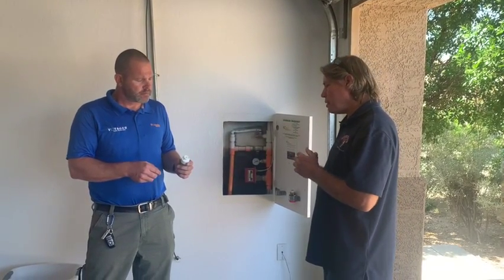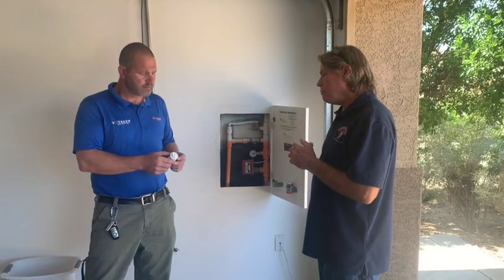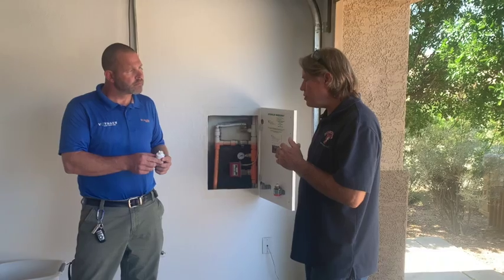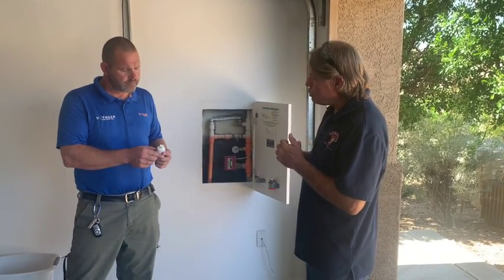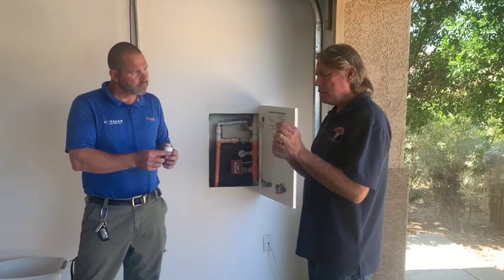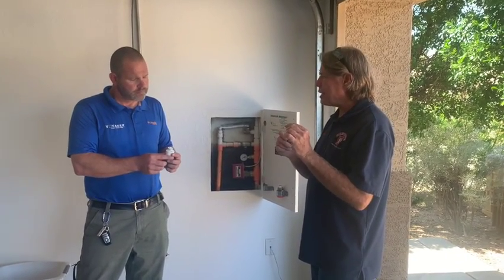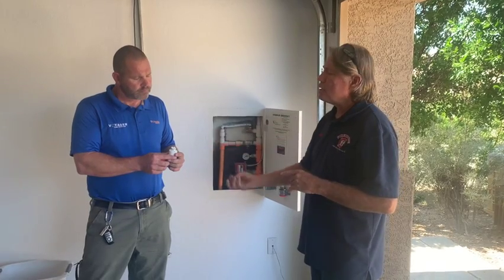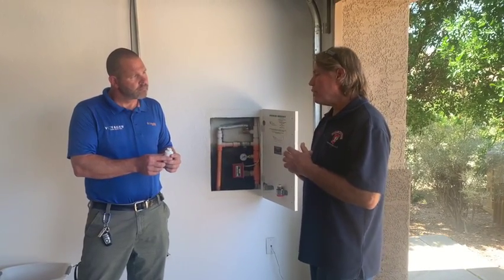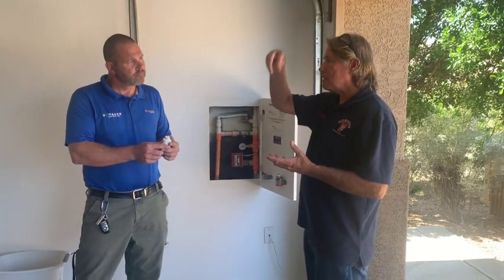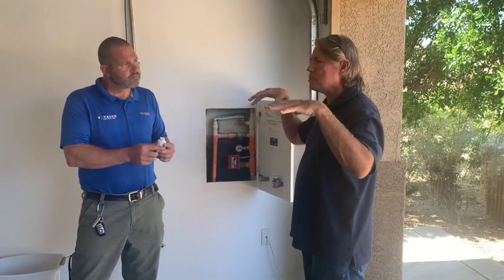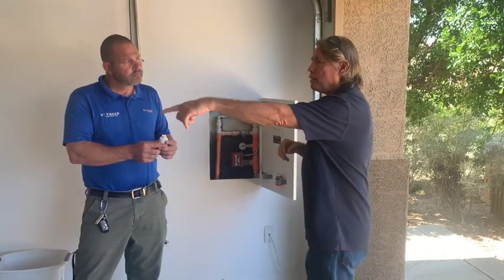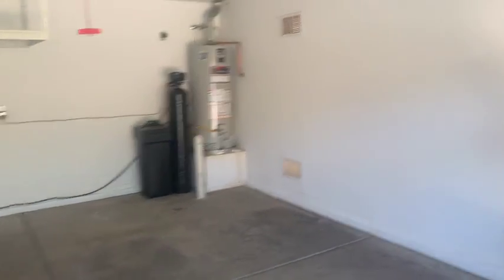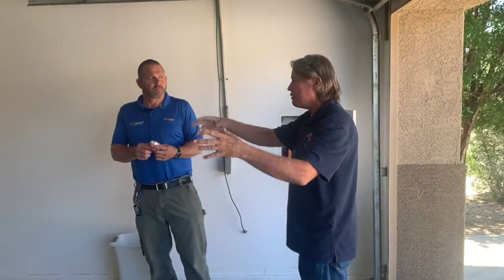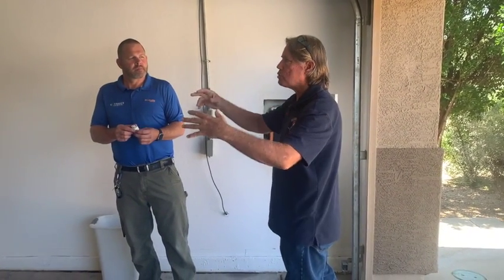Now, this particular type, the brand name is a Viking. It is a fusible link type head, so at 162 degrees, that head will deploy by virtue of solder that melts at that temperature. Then it'll release the mechanisms and allow the head to deploy. At that point, you get about 30 gallons a minute hitting a deflector that spans out in about a 10-foot radius, and it will only act individually. So if you had a fire over here in this area, for example, one head would deploy, the other head would only deploy if that head was overcome. If that sprinkler was overcome by the fire, then the second sprinkler would deploy.